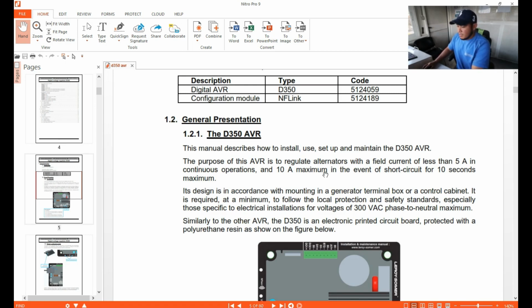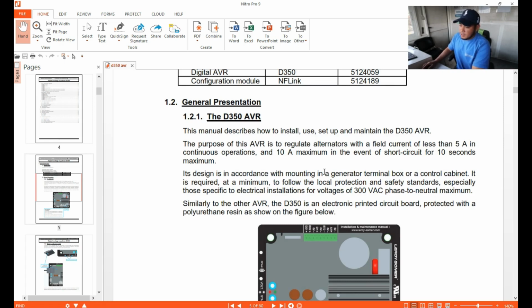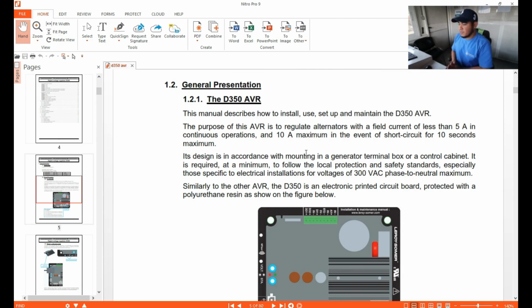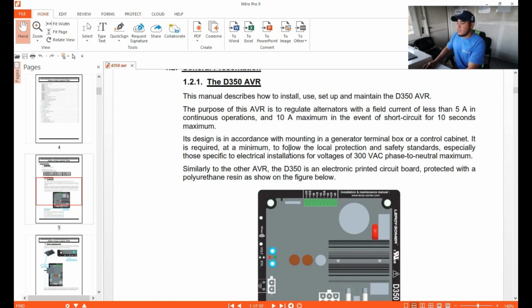The D350 AVR manual describes how to install, set up and maintain the D350 AVR. The purpose of the AVR is to regulate alternators with field currents of less than 5 amps. The most common AVRs use 5 amps, and the maximum is 10 amps only for split seconds, around 10 seconds, for a short circuit. That is standard for all AVRs, I think, and it is designed for mounting in the generator terminal box or the controls cabinet.